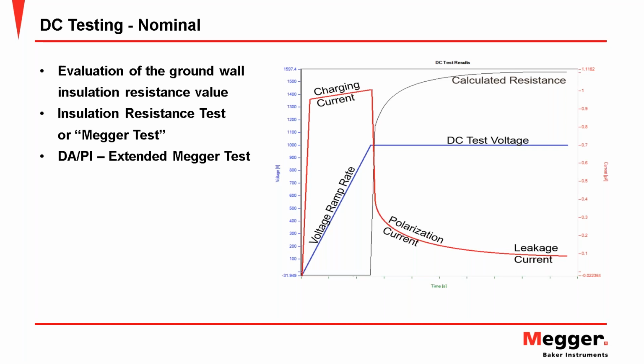The DC tests, again, we're probably very familiar with MEGGER testing or insulation resistance testing at or around the nameplate of the motor. So if I have a 460 volt motor, for example, typically we measure that at 500 volts. Some folks measure that maybe at 1,000 volts, but it's not intended to be a stressful test on the insulation. It's just an evaluation of the ground wall resistance value. That value can be measured and quantified so that we can compare it to standards, or we can compare it to past readings and see how that insulation resistance is varying over time.